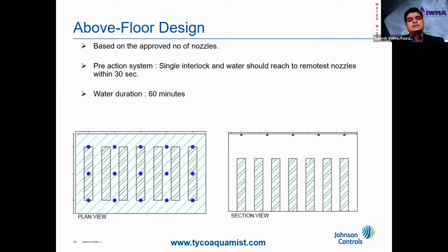When we talk about the design for the above floor area, it is purely based upon the number of nozzles approved during the testing. We can protect this area either with the wet application method, or with a non-interlock or a single interlock pre-action system. We used a single interlock pre-action system where the water should reach the farthest point within 30 seconds, and water should be available for 60 minutes of duration.